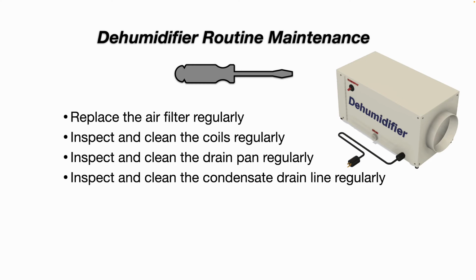And we want to talk about dehumidifier routine maintenance. So if you have a dehumidifier or you're going to buy one, it is not a set it and forget it device, right? Just like any HVAC equipment, or really any equipment, does require periodic inspection and maintenance. For example, you'll need to replace the air filter regularly, inspect and clean the coils, because inside the dehumidifier there's an evaporator coil, and then you have your condenser coil. You want to inspect and clean the drain pan, which sits directly below your coils. Inspect and clean the condensate drain line regularly, because again, you don't want mold and bacteria and dust and dirt accumulating anywhere in these items. Keep everything clean, keeps your water quality clean.